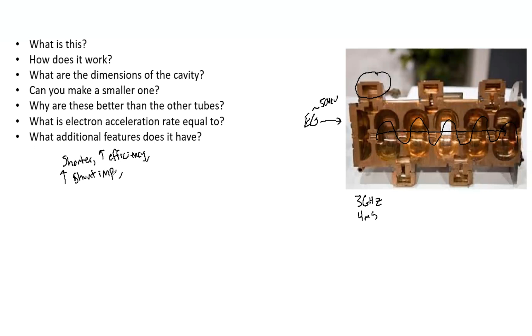There is a better shunt impedance. That means that essentially a better shunt impedance means you have a better efficiency to turning the RF power to accelerating gradient. And then also this reduces the dose rate by 20%. So that's not an advantage but something also to note - it does have a small disadvantage compared to the traveling wave.